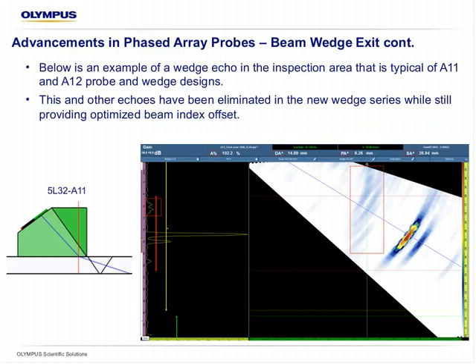Wedge echoes from the corner of the wedge, and again, some of the probes and wedges, depending on the aperture that is programmed, allow the operator to create a situation where it's obstructed. This can be reduced or eliminated by changing the aperture or moving the aperture back a few elements from the probe. In some cases, these can't be eliminated because they come from the probe housing or from the back of the wedge. Most customers wouldn't recognize this for what it is, but know it interferes with their inspection and causes them problems in their calibration, and we'll see a big improvement.